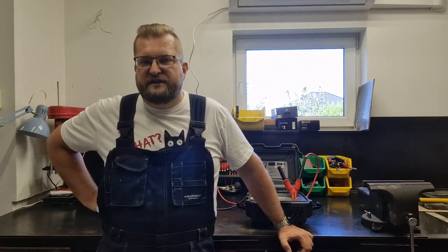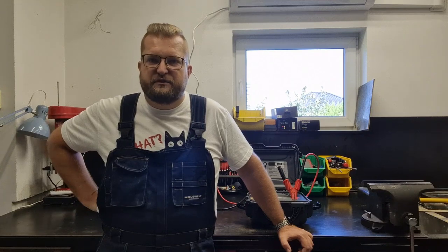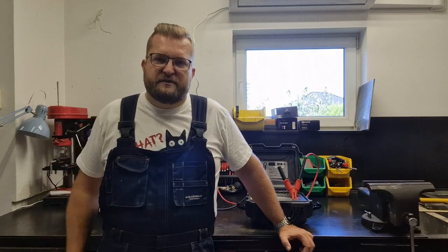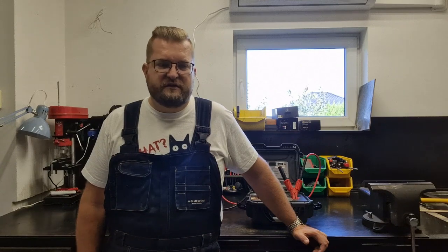Of course, we can check the graph of the insulation through time, and based on this determine if there is any moisture inside or some problems with insulation for the future. But partial discharge indication also gives some additional information if some phenomena of partial discharge appear in the cable, and sooner or later this insulation will be damaged. So it's better to prevent than pay for failures and additional cost.